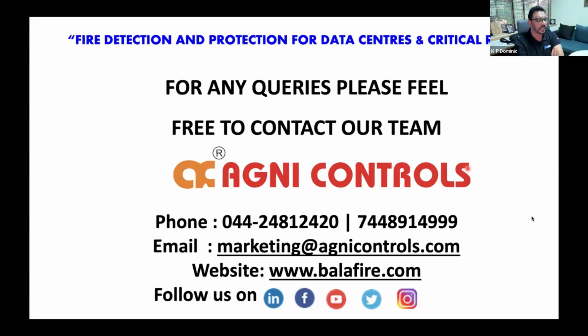Yeah, for a data center, you have a false floor, false ceiling, and true ceiling. Aspiration is the best way of detecting smoke, but a flame detector has to be positioned. In many cases, we don't recommend it. I don't know the reason. It has to be, as I said, primary and secondary. You should also have the flame detector. That's a perfect design, very sensitive and quick in action. But the spot detector is not recommended for a data center or any critical room. Best is an aspiration system. Earlier it was very expensive. Today, many people are offering the solutions. I would recommend having both in the critical room, aspiration and also flame.